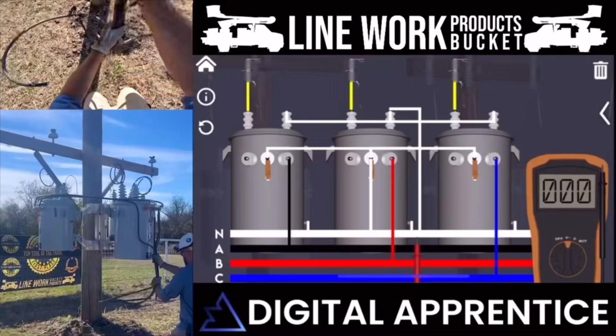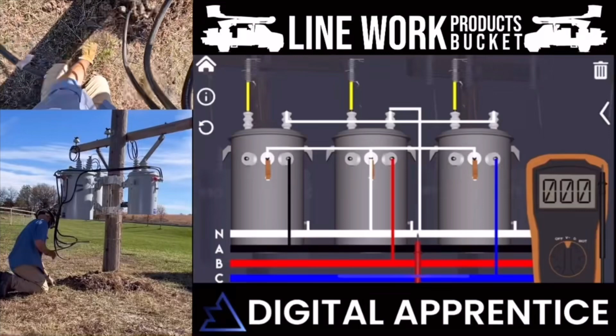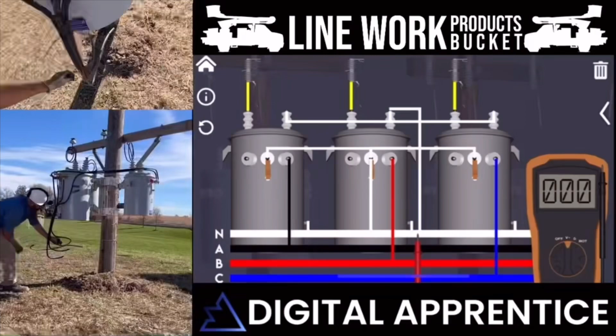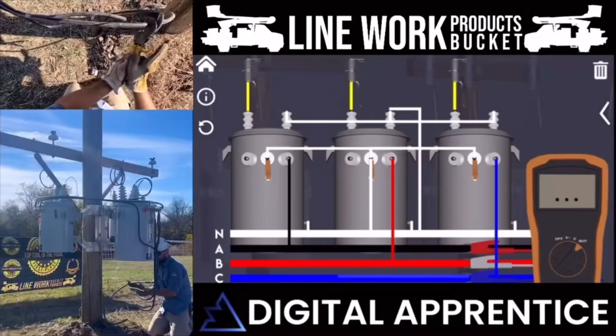So back over to the field demonstration, you see that I got these legs all shaped down nice and clean. On a 120-208 bank, or any 120-240 banks, I like to put the neutral high and then drop the legs underneath the neutral for the connections. And then on 480 and 277/480 transformer banks, I go neutral low and put the hot legs above the neutral. And that helps the troublemen that are going to be troubleshooting these down the road verify whether it's a 120-208 or a 277/480 transformer bank. It's just a little step that you can do to help the guys that are going to be taking care of this stuff in the trouble department.